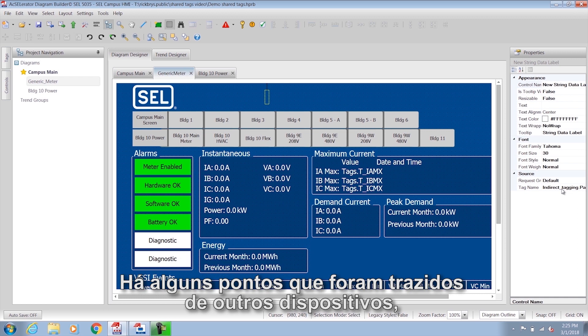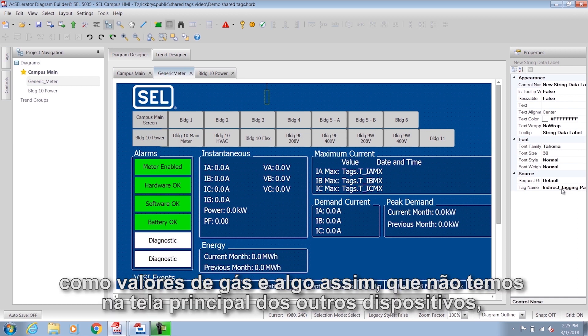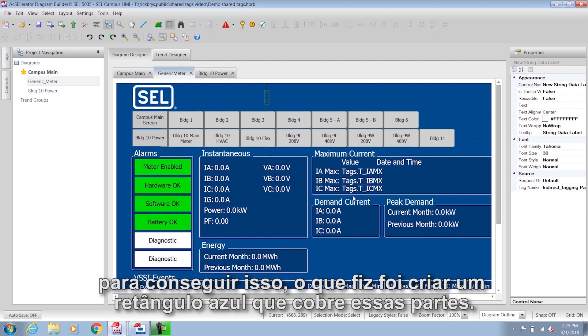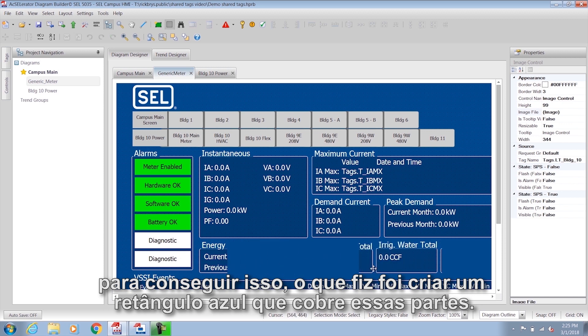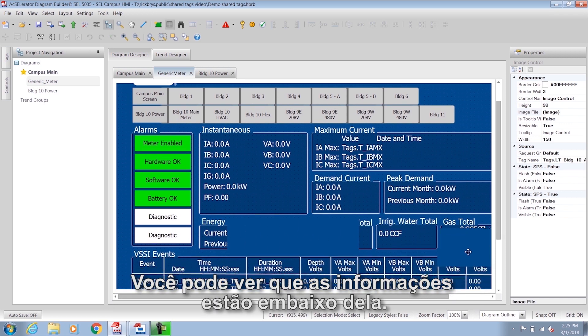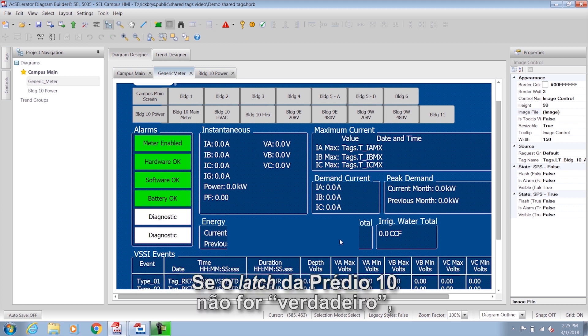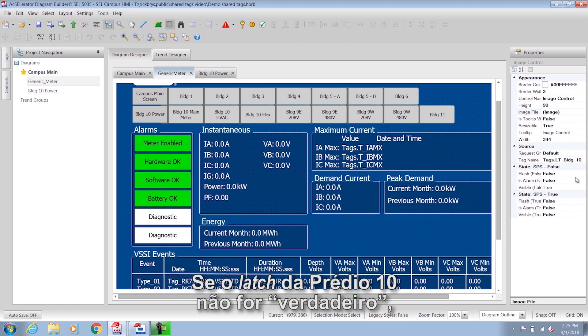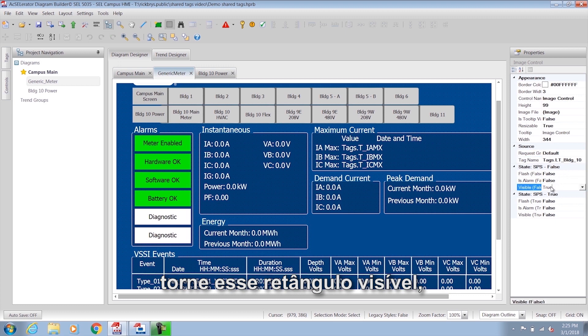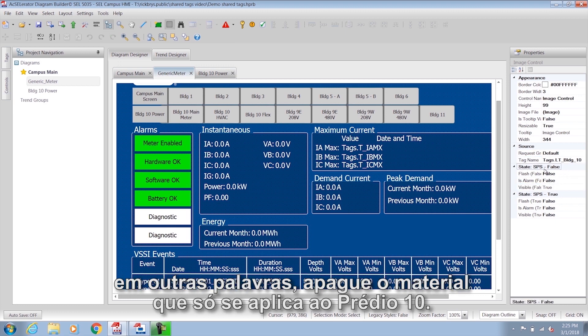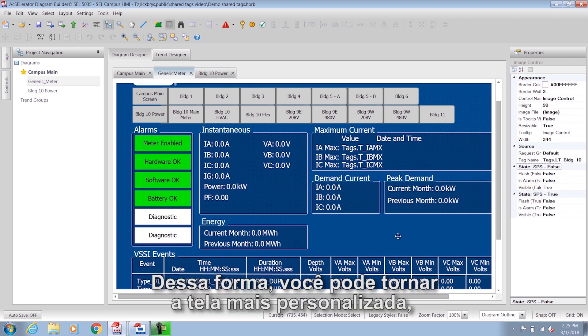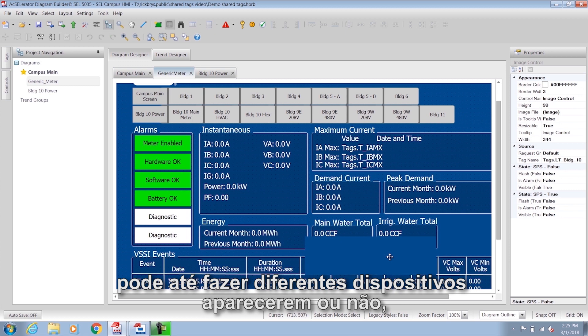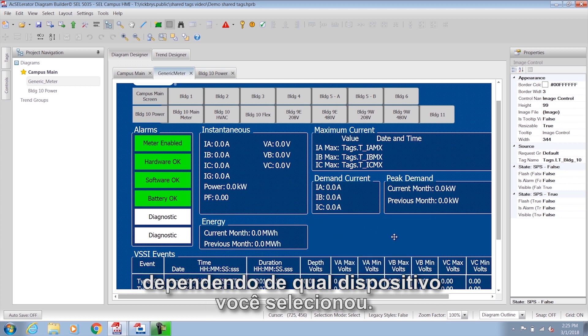There are a couple of data points brought in from other devices, like gas values, that we don't have on the main screen for other devices. To handle that, I made a blue box that covers those parts. If building 10 is not selected, that box is made visible — effectively blanking out the stuff that only applies to building 10. In that way, you can make the screen very customizable, and even make different elements appear or not appear depending on which device you've selected.